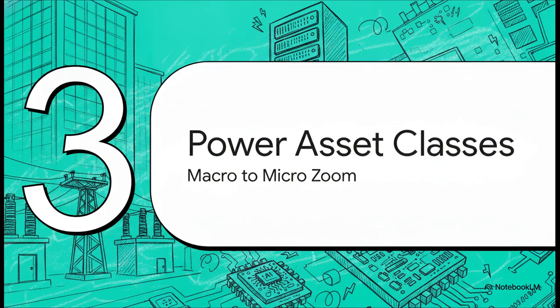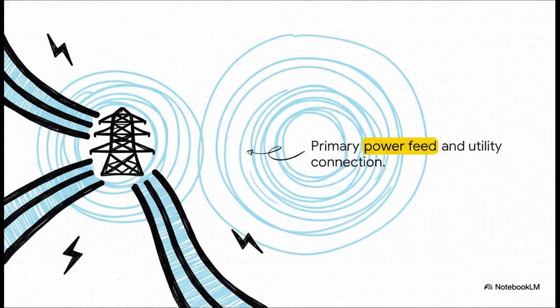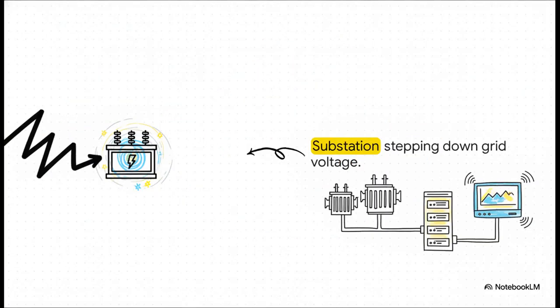Okay, part 3, tracking power asset classes. Let's do a macro to micro zoom. We're going to go on a rapid-fire visual breakdown starting from the outside in. At the absolute macro level, we have the primary power feed. This is the massive incoming utility grid connection, or maybe an on-site generation source. This is where all the immense energy for our AI operations first enters the story. So naturally, it's the very first asset class we need to measure. Moving one step closer into the facility, we hit the substations and transformers.